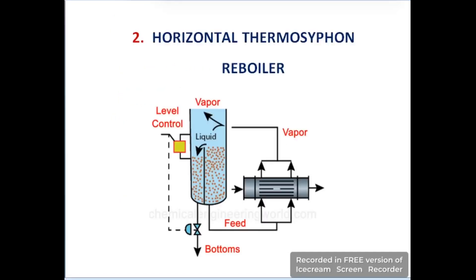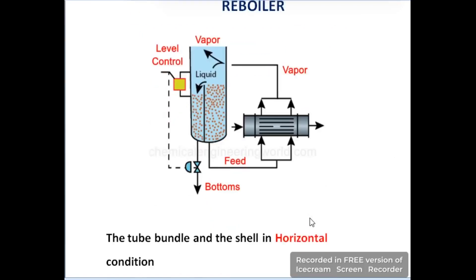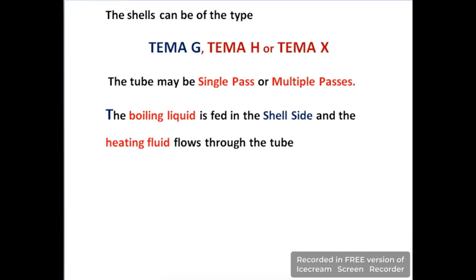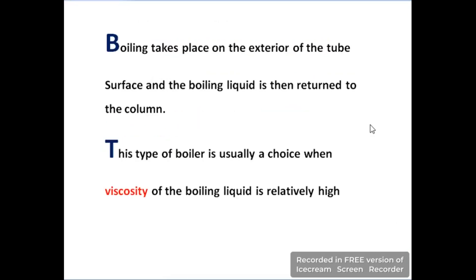The second type is the horizontal thermosyphon reboiler. Here you can see the tube bundle and the shell are both in a horizontal position. In this reboiler, the heating fluid and boiling fluid have opposite flow arrangements in the shell and tubes compared to vertical reboilers. Boiling takes place on the exterior of the tube surface, as the boiling liquid flows in the shell. After getting heat, it converts into vapor phase and the vapors go into the distillation column. This type of reboiler is used for liquids which have high viscosity.